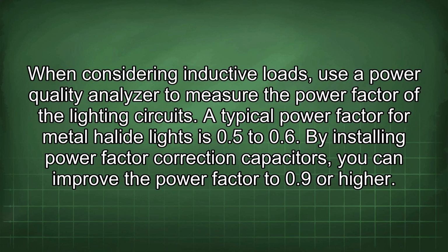When considering inductive loads, use a power quality analyzer to measure the power factor of the lighting circuits. A typical power factor for metal halide lights is 0.5 to 0.6. By installing power factor correction capacitors, you can improve the power factor to 0.9 or higher.